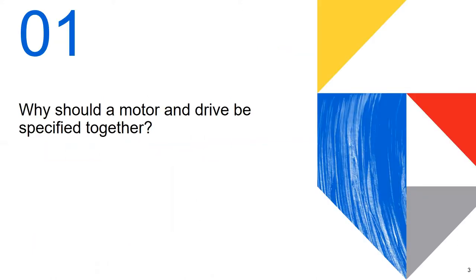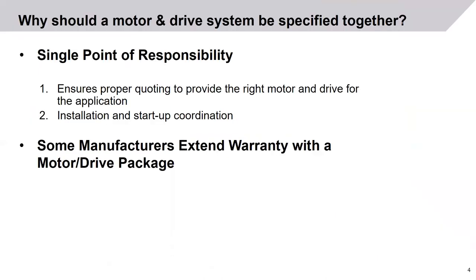Why should a motor and drive be specified together? Single point of responsibility ensures proper quoting to provide the right motor and drive for the application, as well as installation and startup coordination. Also, some manufacturers will extend warranty with a motor and drive package.